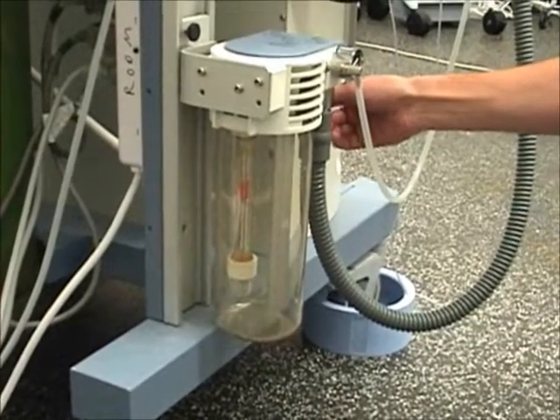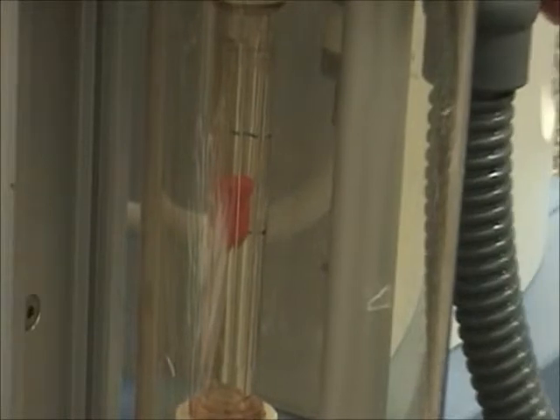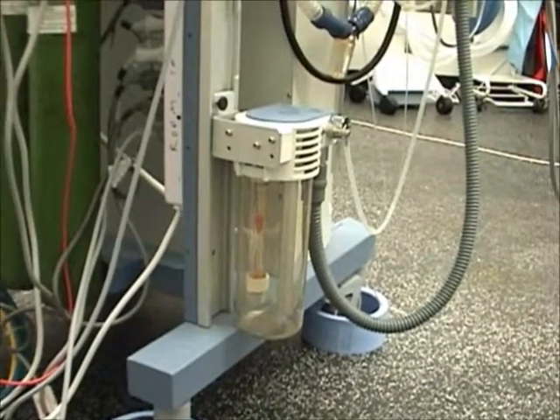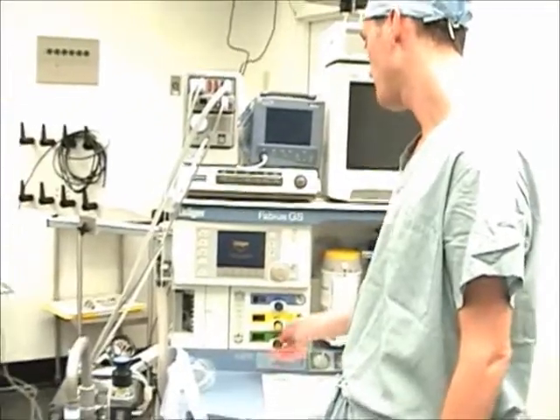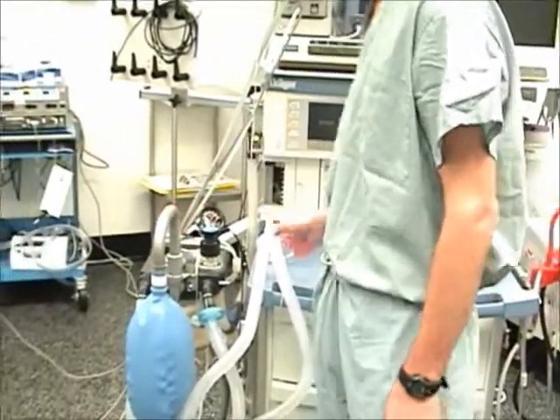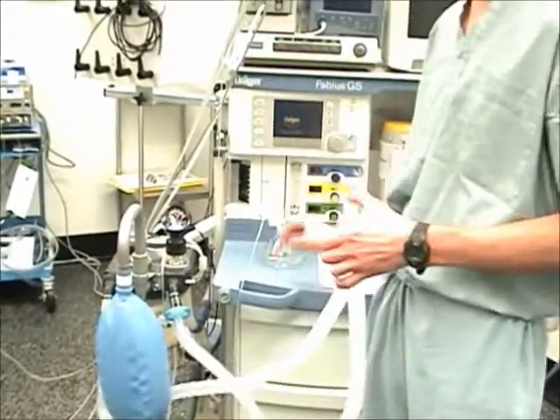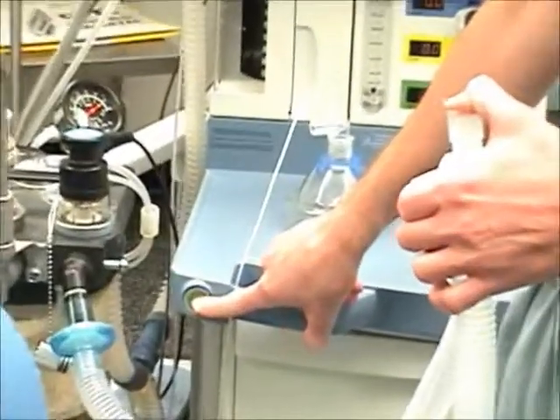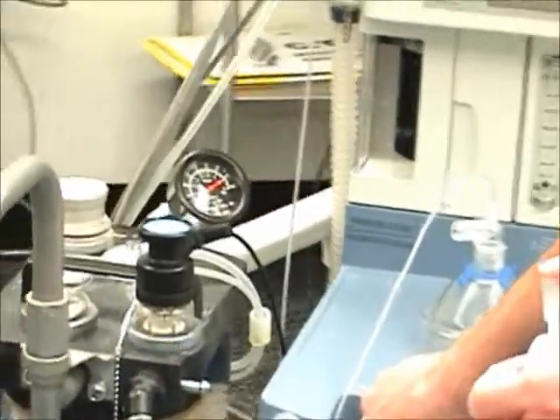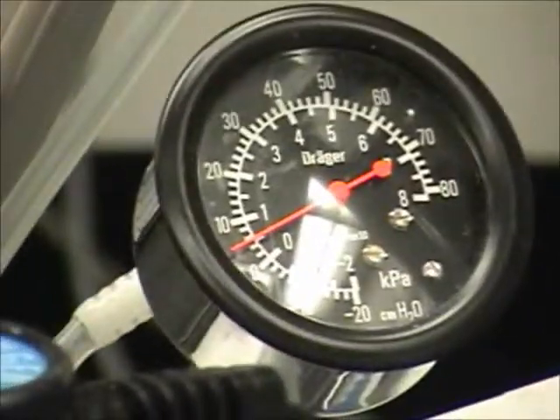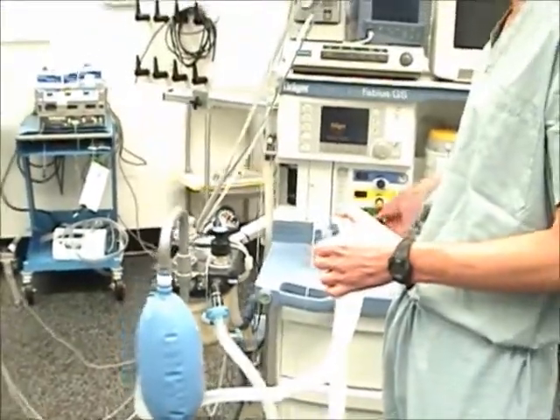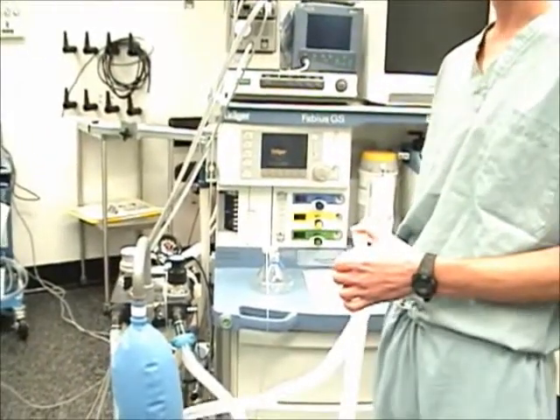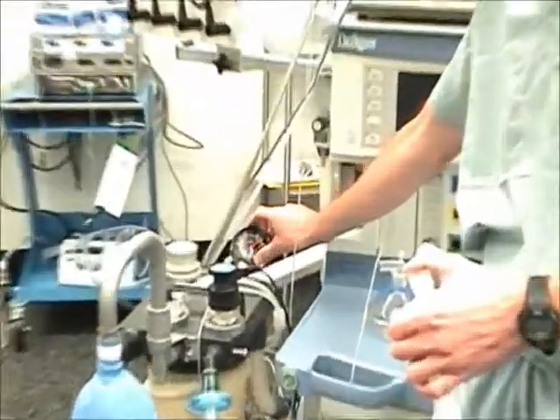Adjust the waste vacuum so that the float is between the minimum and maximum markings on the chamber. With all gas metering valves closed and the APL valve fully open, occlude the Y piece and press the O2 flush. The circuit pressure should be less than 10 centimeters water. We're reading 5 centimeters water. With the Y piece still occluded and the metering valves off, circuit pressure should be greater than minus 0.5 centimeter water. We're at just above 0.